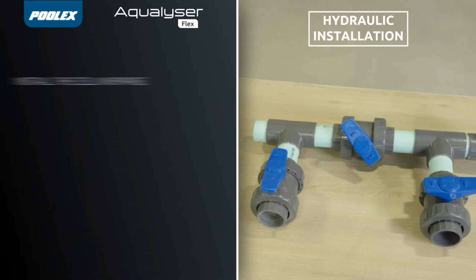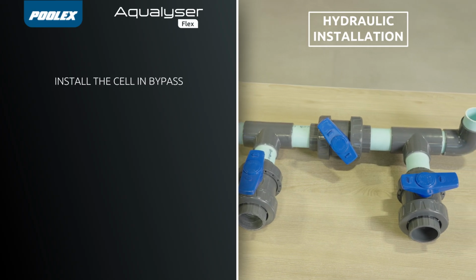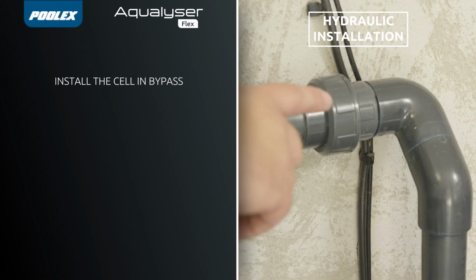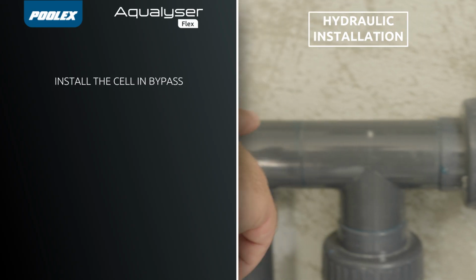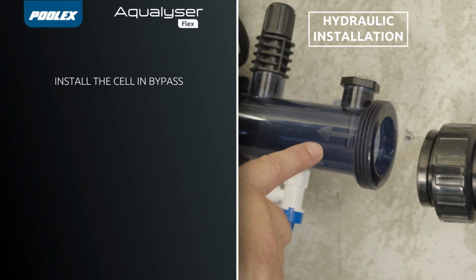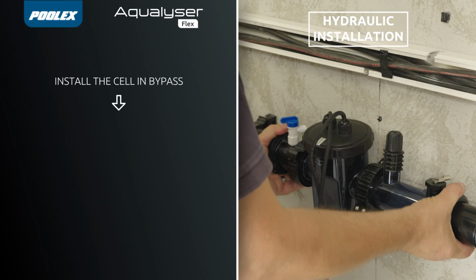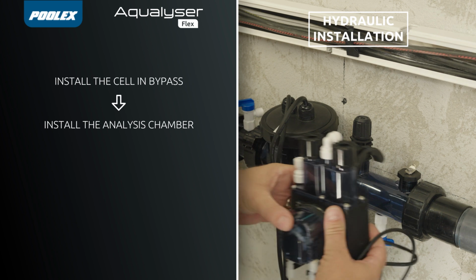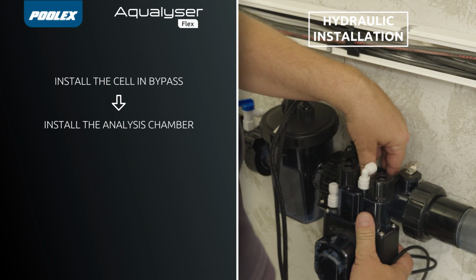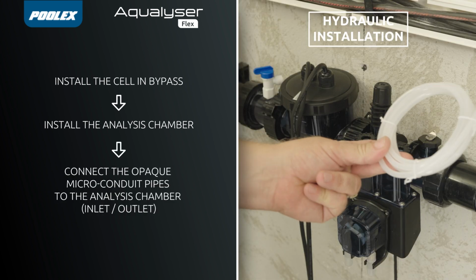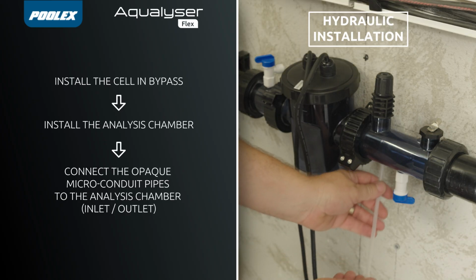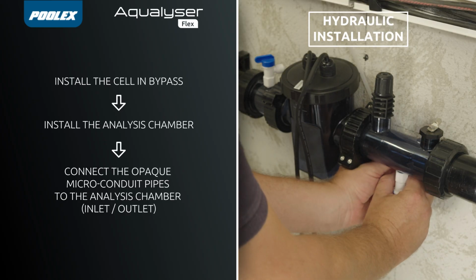Install the Aqualyser Flex in bypass on the return pipe after the heating system. Respect the direction of water flow using the arrow. Install the analysis chamber on the left or right, depending on the configuration of your technical room. Connect the suction and discharge tubes of the analysis chamber.